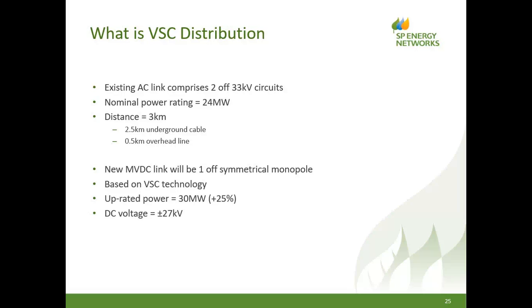So the concept is we are not stressing the existing AC cables any harder than they're already stressed under the AC voltage. In theory, we could push the voltage higher with DC and get more power. But as I say, we've adopted a prudent approach for this first medium voltage DC link in the UK. So that is the reason for the 27 kV choice of DC voltage. If we go to the next slide.